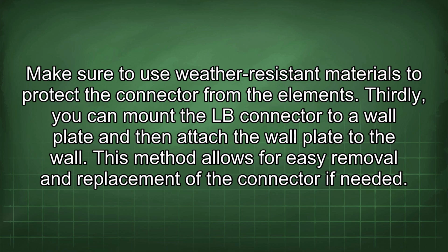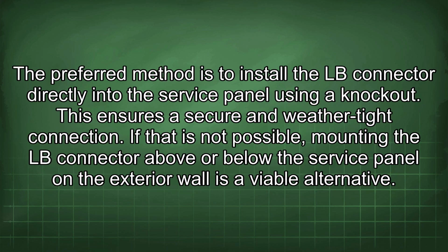Thirdly, you can mount the LB connector to a wall plate and then attach the wall plate to the wall. This method allows for easy removal and replacement of the connector if needed. The preferred method is to install the LB connector directly into the service panel using a knockout. This ensures a secure and weather-tight connection.